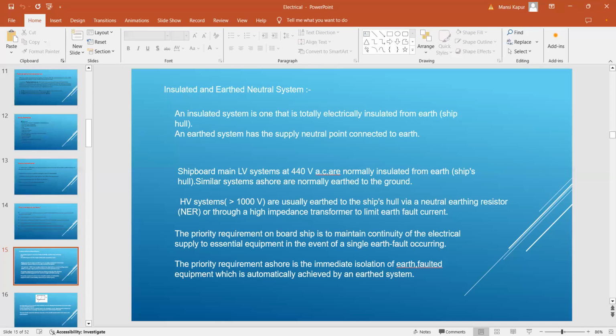Similarly ashore, if you see a similar 440 volt system, they are using the earthed system. Why? That we will see later. But if you are sailing on a high voltage ship, like your container vessel, most of them are high voltage now. So they are using a system known as neutral earth resistor and a high impedance transformer to limit the earth fault current. The priority requirement on board the ship is to maintain the continuity of the electrical supply. So if you use an earth neutral system, what is going to happen?